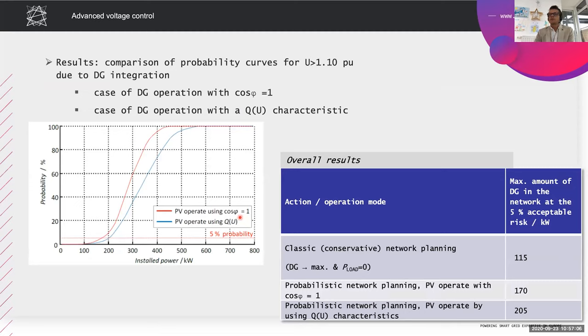For the end, I will show you just some results. Again, a case we were dealing with. And this is the hosting capacity of a low voltage network in case of distributed generation. And you again obtain the hosting capacity in terms of probability curves. The hosting capacity means simply how much distributed generation can you connect to a network without going into problems with voltage levels. Say you take the same network and you use the classic or conservative network planning, when you observe the worst case scenarios. In this case, you will get the result that the amount of DG you can connect to this network is 115 kilowatts. So 115 kilowatts of DG can be connected to this network without violating the voltage limits.